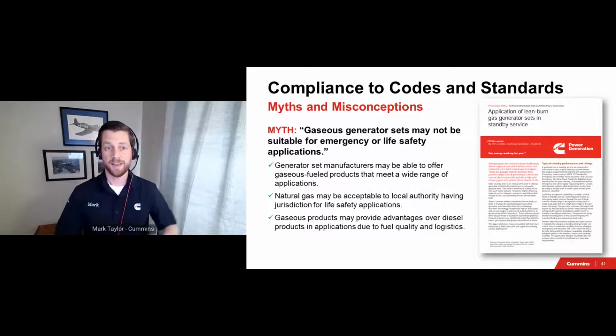So with that, I hope you take away that the notion that gaseous fuel generator sets not being acceptable for standby applications is indeed a myth. Don't rule them out with a broad stroke. ISO 8528 and NFPA 110 certainly do not. Base that decision on the individual performance of the product based on your performance-based specifications.